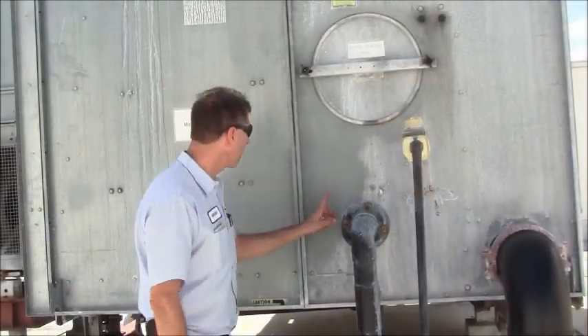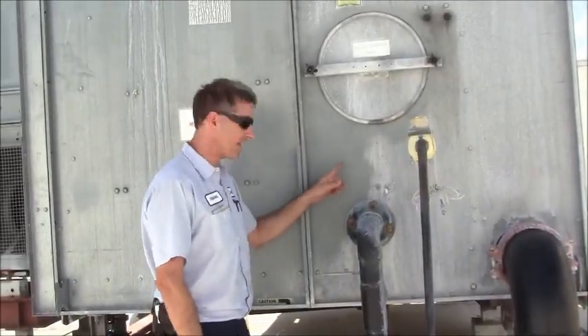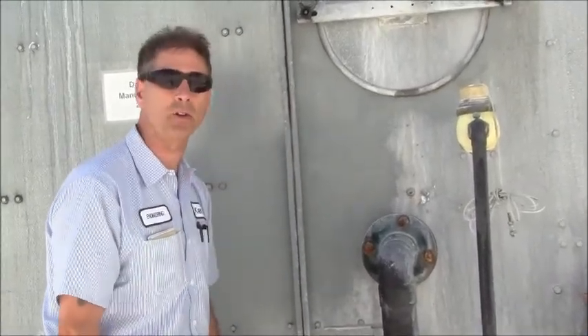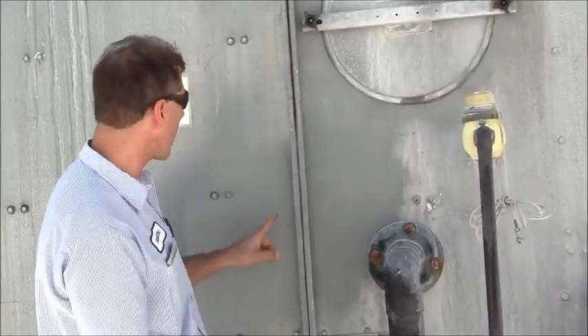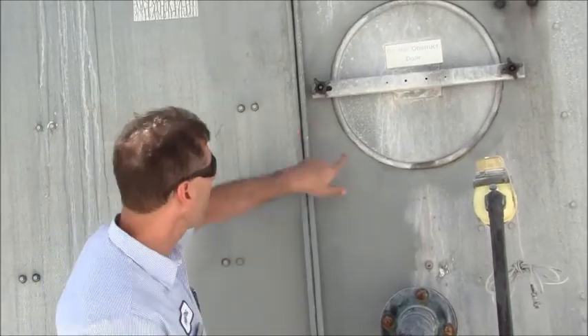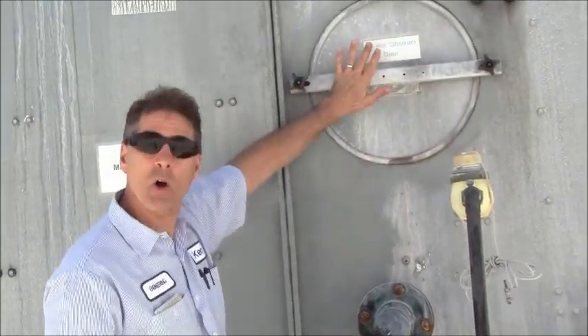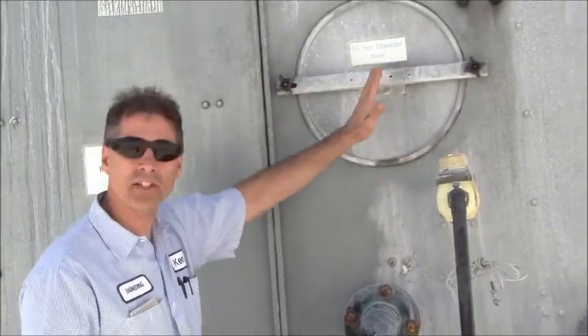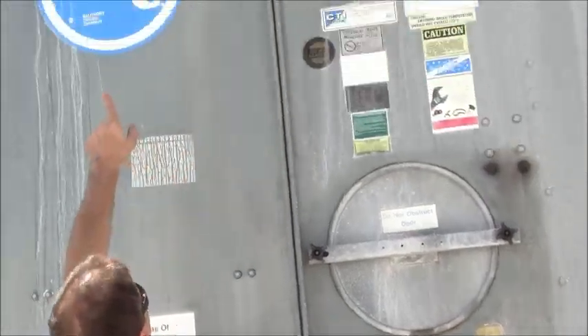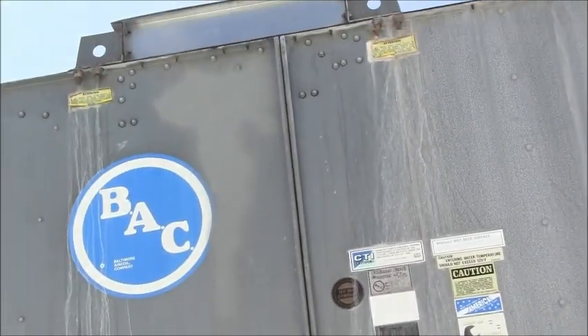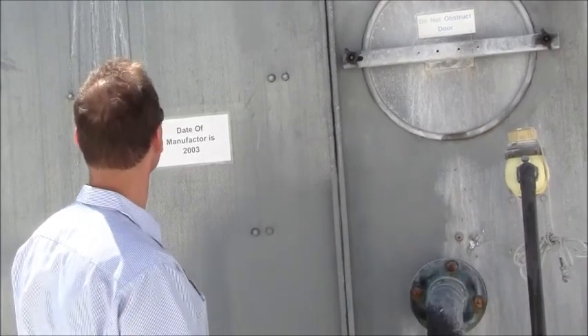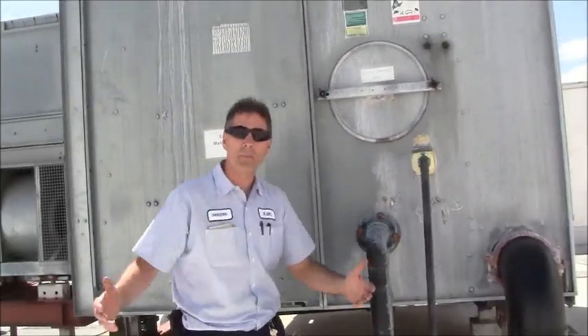All right, here we are. Originally we were leaking right here—it was leaking right down to the ground. But everything is dry here and here. Around the manhole opening is all nice and dry, no leaks coming down. And up top there, where we had some repairs done, that's in good condition. So basically that concludes the repairs on cooling tower number 2.